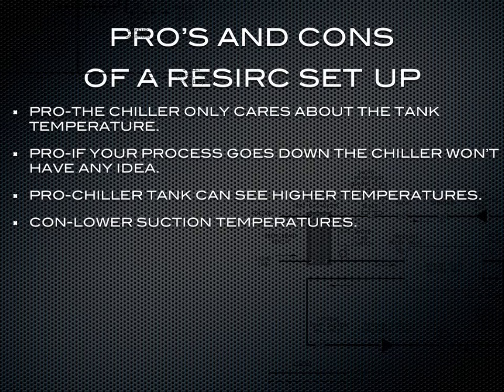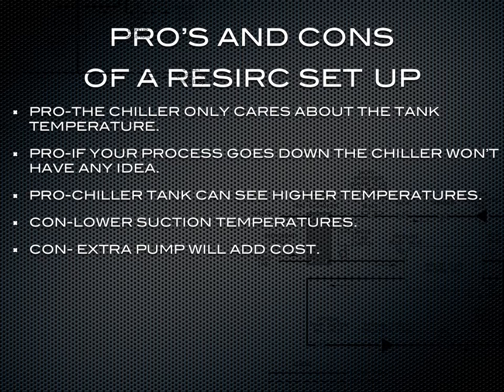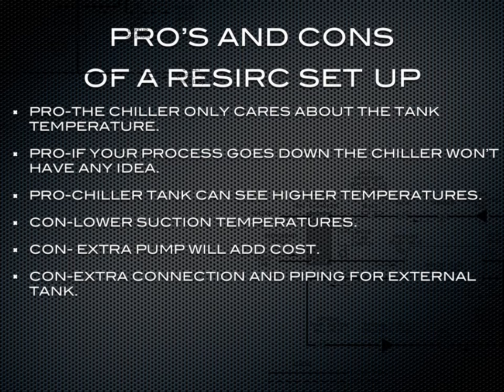On a once-through, there's going to be around a 5°F temperature difference between the refrigerant temperature and your desired leaving water temperature. On a recirc tank setup, there's going to be around an 8 to 10°F temperature difference between the refrigerant and your desired leaving water temperature, so you're going to have less capacity on your chiller. Another con is you're going to need an extra pump, which adds cost. And another con is there will need to be an extra connection and piping for an external tank — on a once-through there's one in and one out, but on a recirc there are two ins and two outs because you're creating two separate loops.